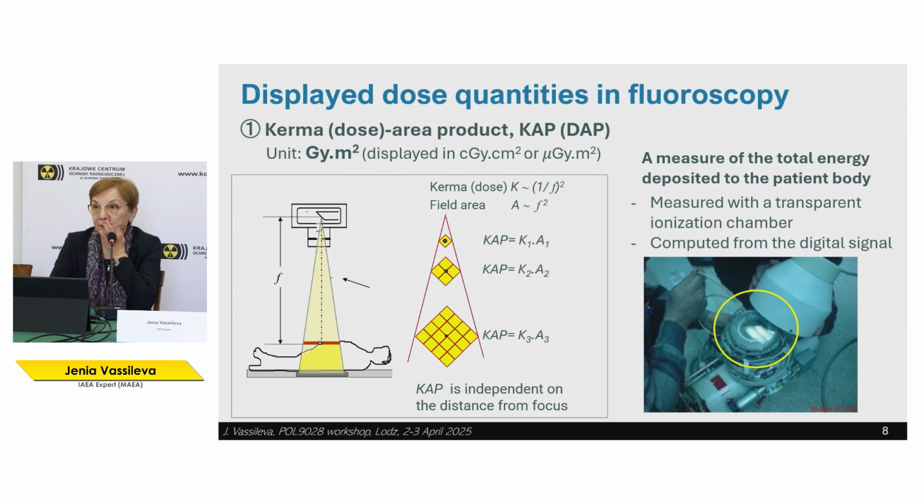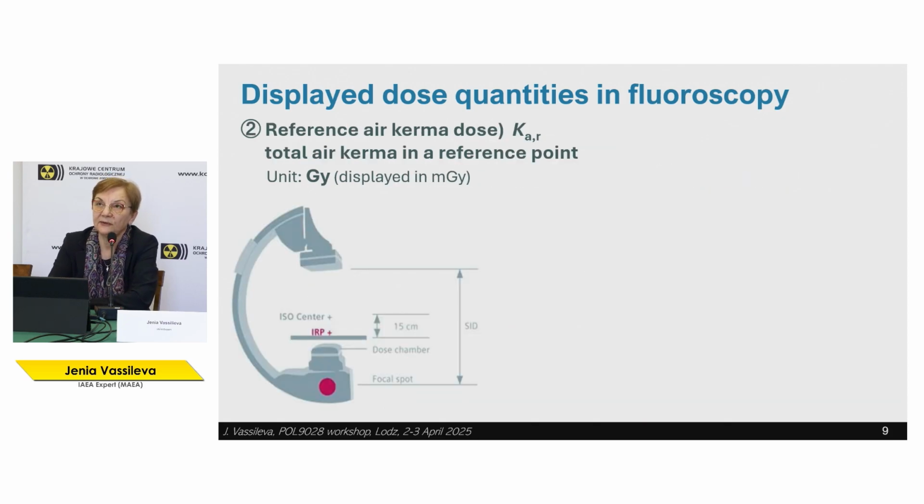So all new equipment should have this integrated, either a physical chamber like this, or in the new flat panel detector systems, it's computed from the digital signal. It does not need to be a measuring device, but still the same quantity is integrated.